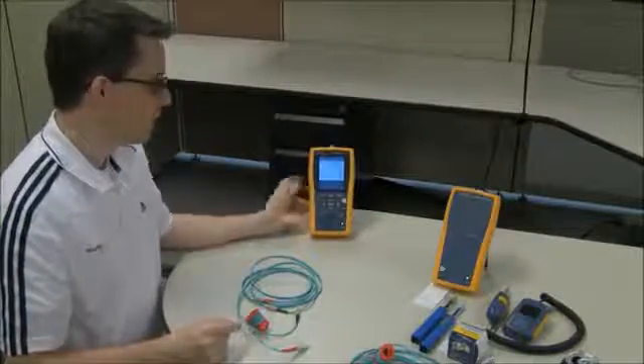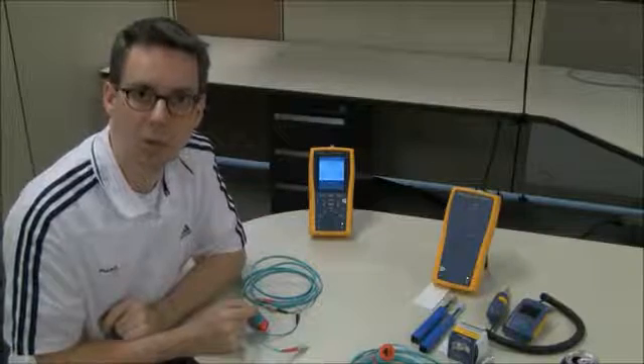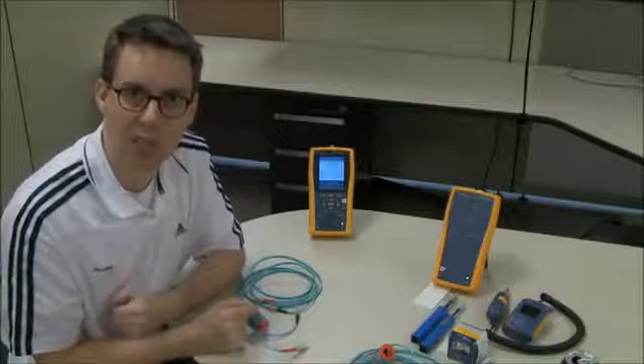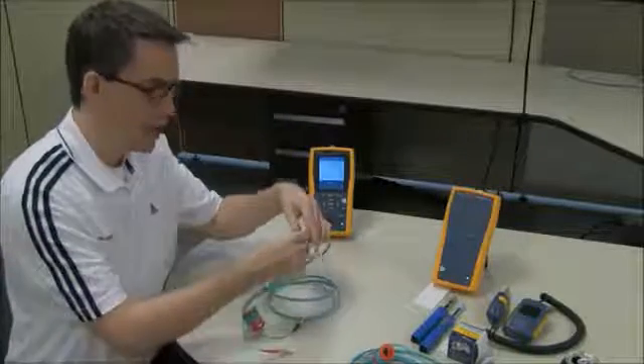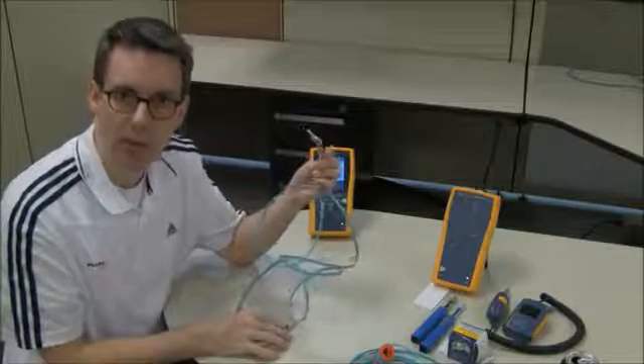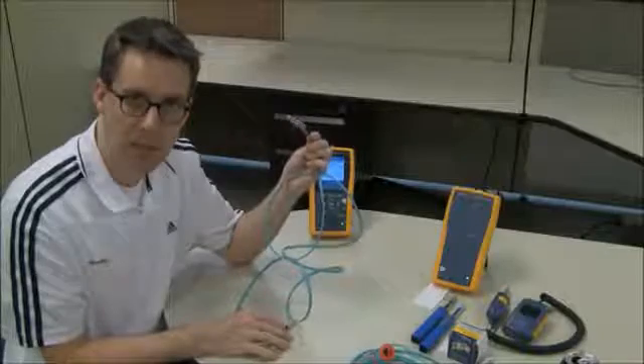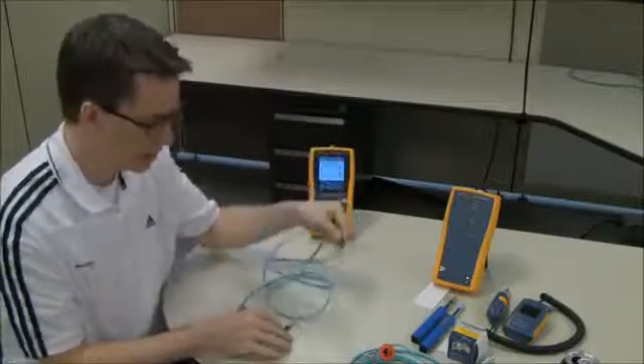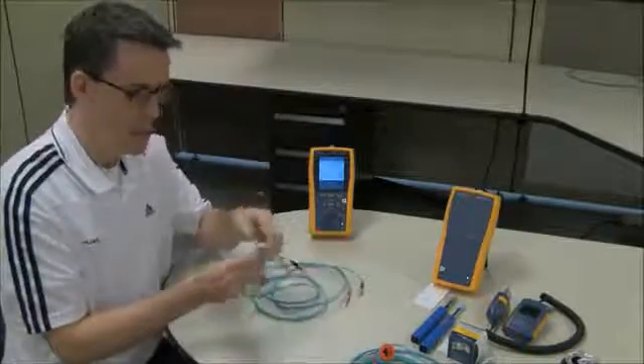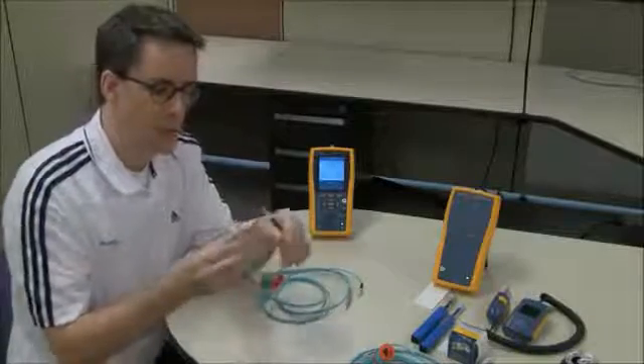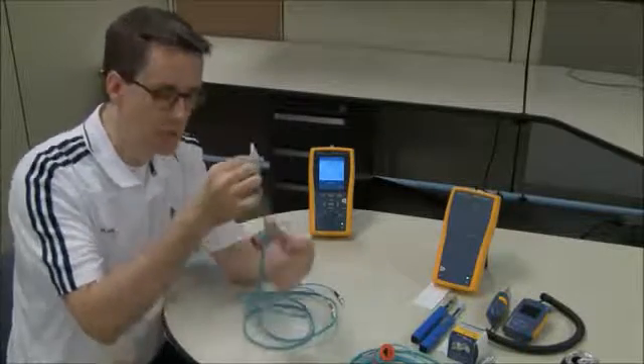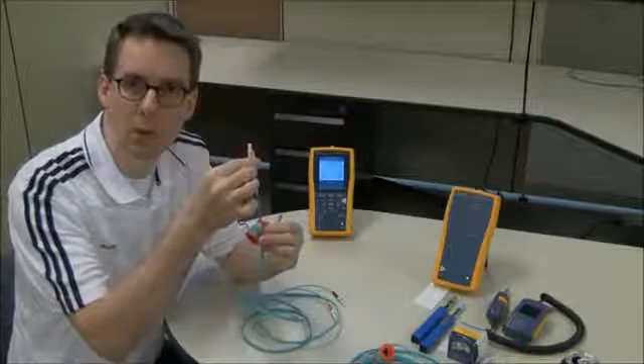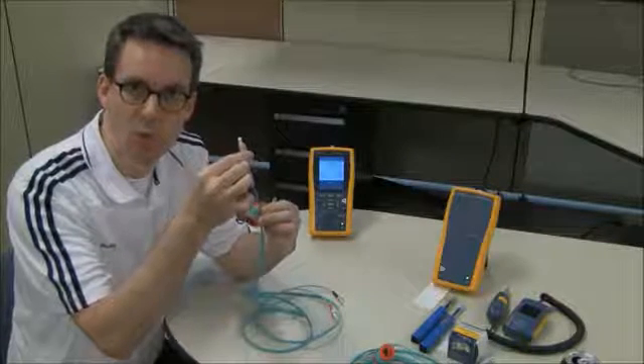In order to do a OneJumper reference, we need to be using hybrid test reference cords, or TRCs. They're hybrid because at one end we have duplex LC, that makes sense, we're testing duplex LC today. The other end, a little bit strange, we have LC, but we also have an SC connector with this red thing on it, which is called a mandrel, and it's critical that you use a mandrel, otherwise your readings are going to be pessimistic.